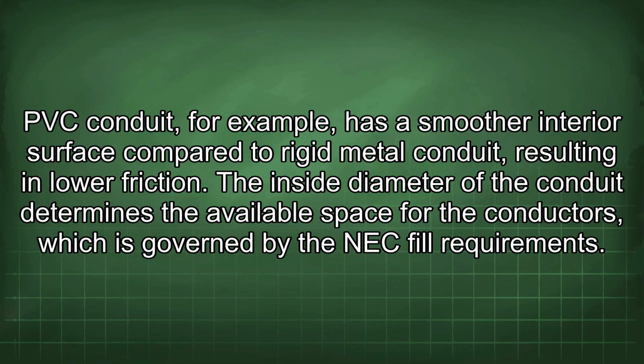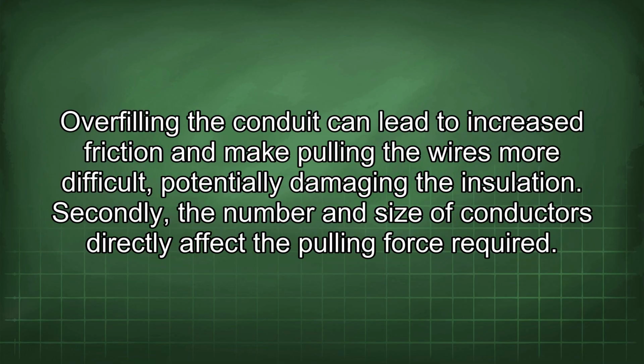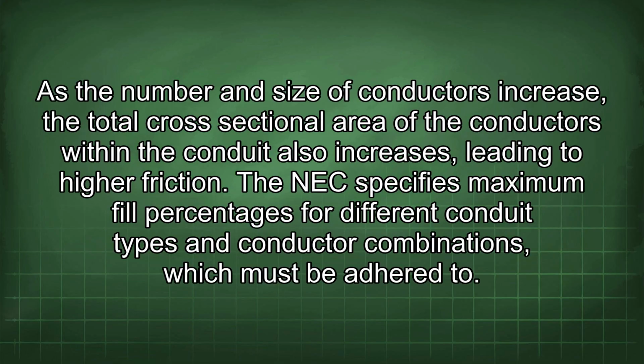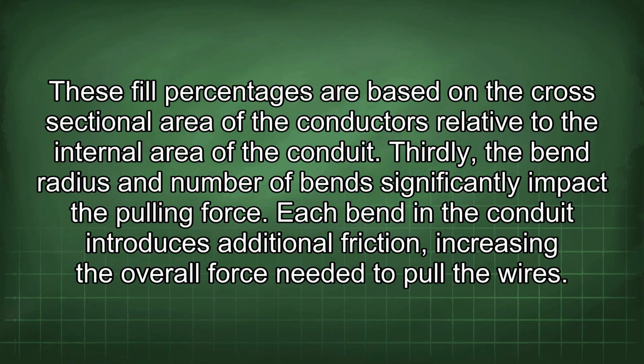The inside diameter of the conduit determines the available space for the conductors, which is governed by the NEC fill requirements. Overfilling the conduit can lead to increased friction and make pulling the wires more difficult, potentially damaging the insulation. Secondly, the number and size of conductors directly affect the pulling force required. As the number and size of conductors increase, the total cross-sectional area of the conductors within the conduit also increases, leading to higher friction. The NEC specifies maximum fill percentages for different conduit types and conductor combinations, which must be adhered to. These fill percentages are based on the cross-sectional area of the conductors relative to the internal area of the conduit. Thirdly, the bend radius and number of bends significantly impact the pulling force.